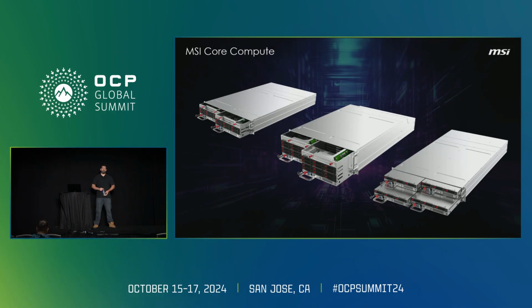And in my opinion, anytime you ship a rack that's full of blanking plates, that's a failure of planning. Those blanking plates could have just been taller heat sinks with fans that don't have to work as hard. So my 3U 2-node chassis lets me fully populate a 42U rack at 17 kilowatts, even without storage, just processors. You're running out of power and space at the same time.